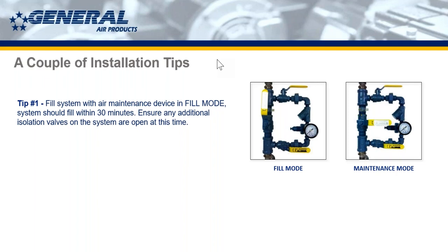Watch that though, if you're using a shop air supply that has really high pressure or really high flow, you can do some damage to the system if you let that go full flow. But that would be outside of what a fire protection air compressor is and more in line with really high-end industrial compressors, which you just don't see as much anymore.